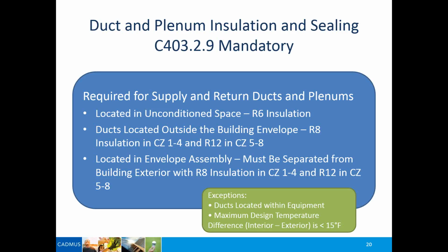The only reason you may consider insulating that ductwork is for condensation reasons, if it is truly in conditioned space and there's an issue with that. But other than that, in conditioned space you don't have to worry about insulating. Outside and in unconditioned space, there's one insulation level, and for ducts completely outside the building, another insulation level.